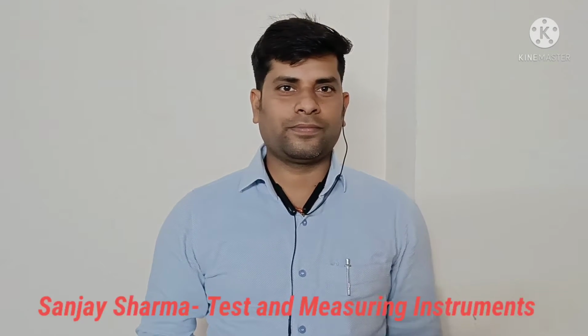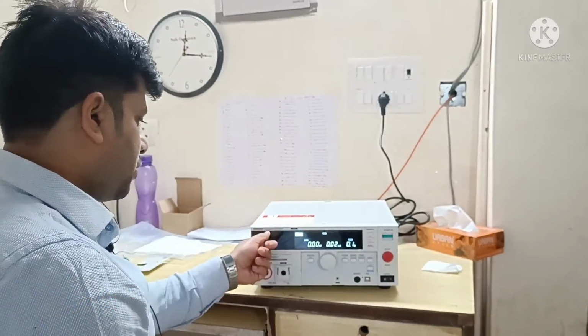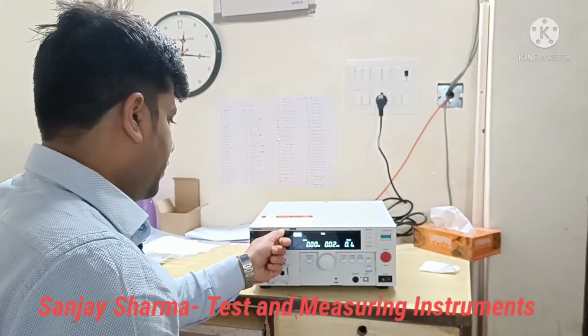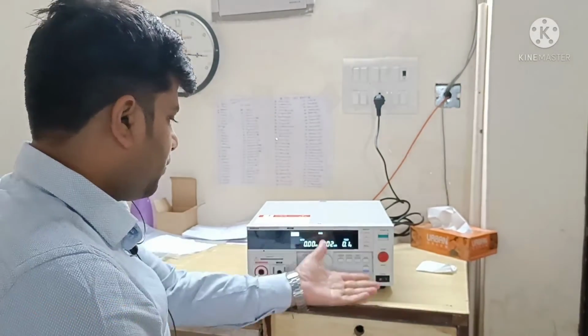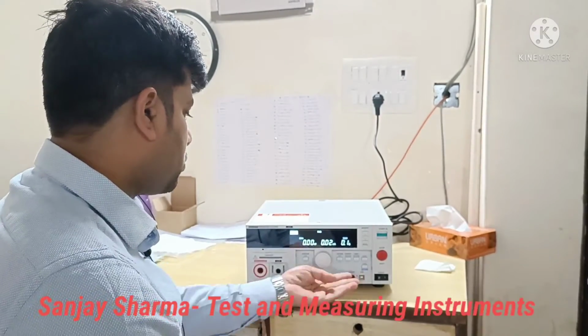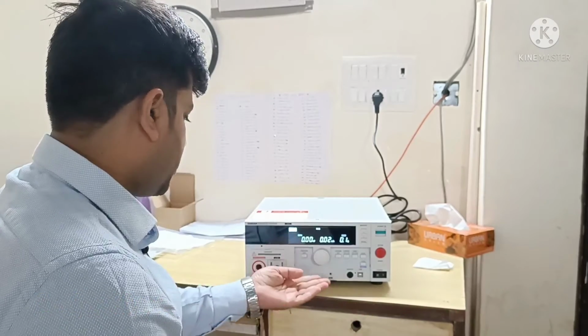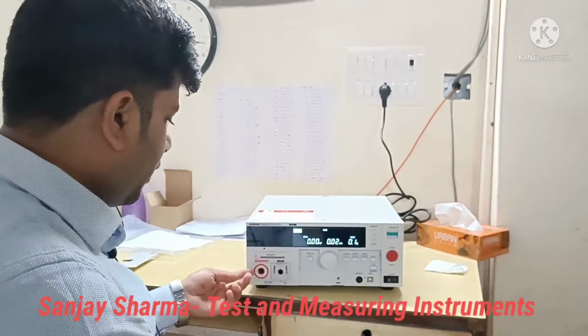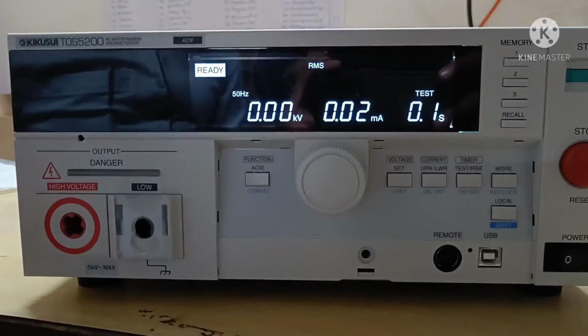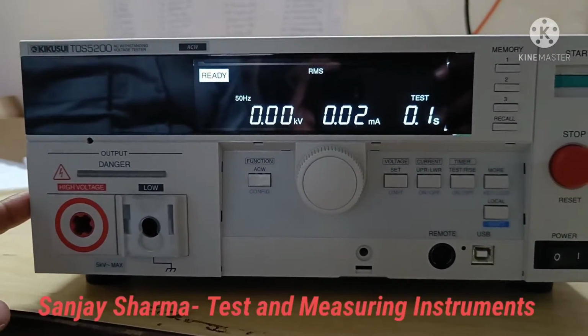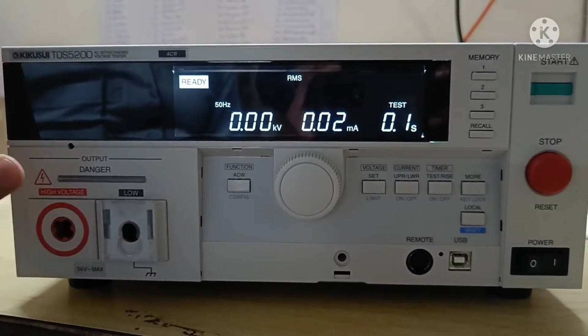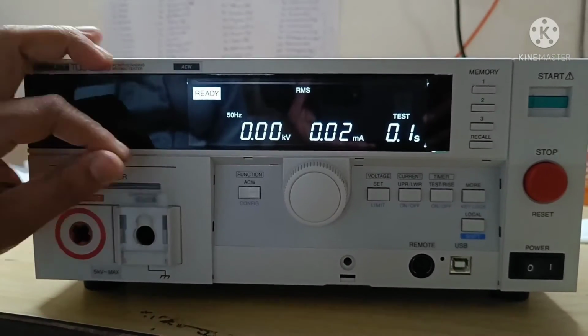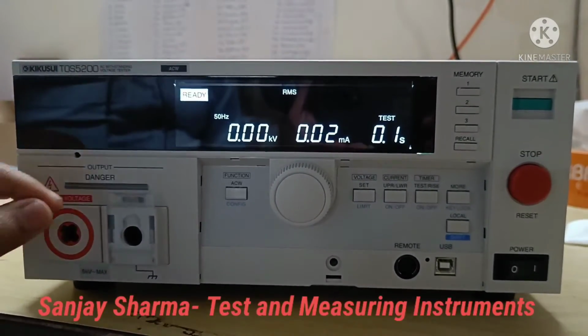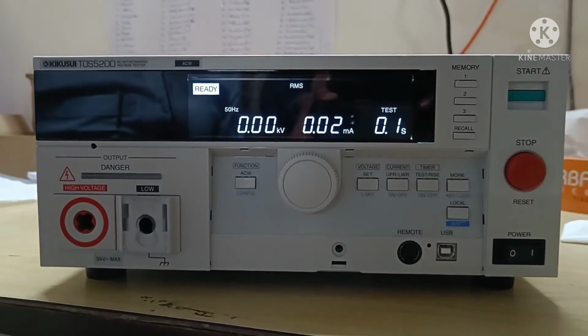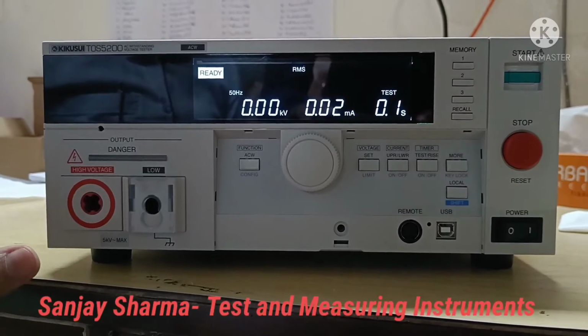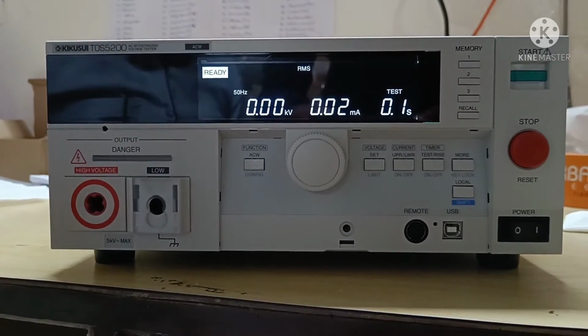Okay, let's start. Here we have the model TOS5200, which is the AC withstanding voltage tester. These are the front panels, with different functions to set the parameters and perform the test. Starting from here, this is the high voltage section where we connect the red probe, and the black probe coming with this instrument needs to be connected here. This is a safety lock. It is very necessary during testing. We need to lock the probe so it is not removed during testing, which protects the users from any hazardous cases.